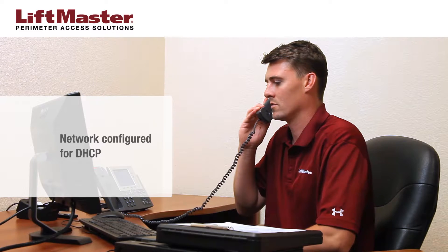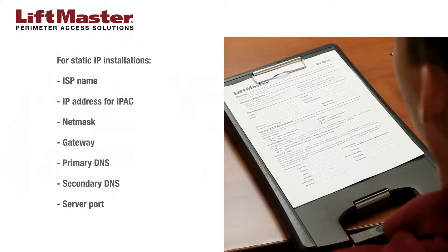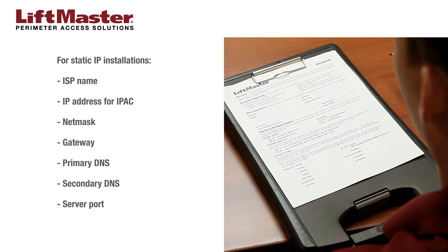The preferred setting for IPAC cloud configuration is DHCP, which automatically negotiates a connection with the local network. However, if the site requires the use of a static IP, make a note of the following information on the site survey form: the name of the internet service provider, the IP address to be assigned to the IPAC, the netmask, the gateway, the primary DNS, and the secondary DNS.